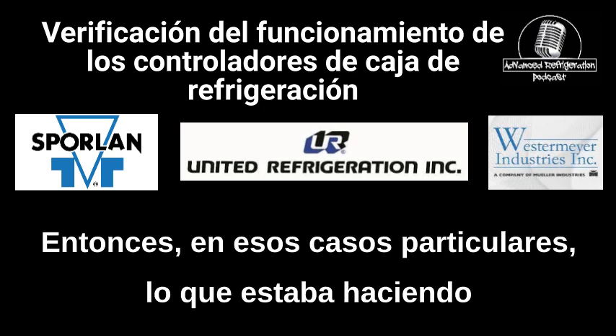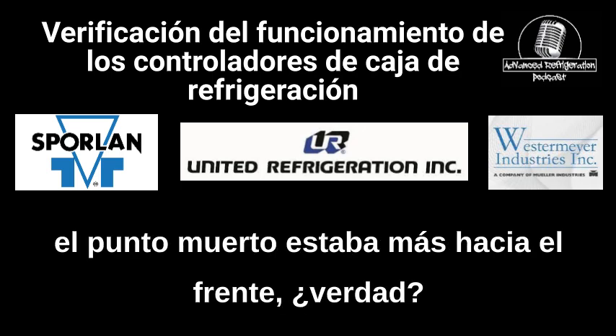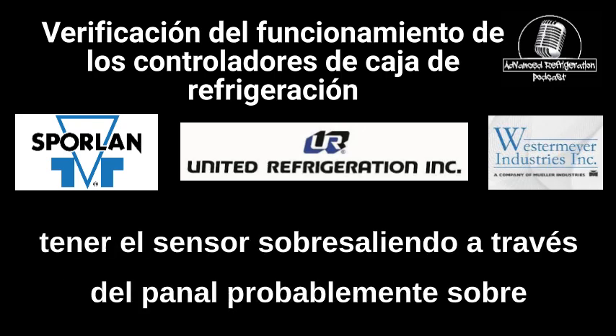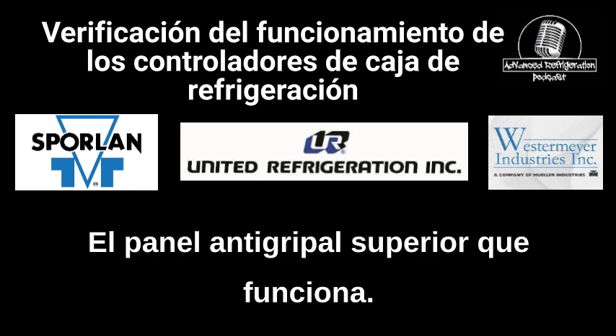On those particular cases, what I was doing was going as close to the back end of the case as possible, because the dead spot was more towards the front, right? So I would put it up in and then have the sensor sticking up through the honeycomb, probably about 1/2 inch to 3/4 inch. So the tip is still getting all that cold air coming out the top flue panel. I mean, that works.